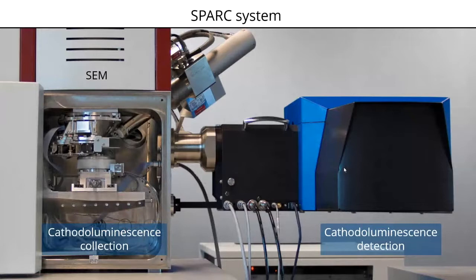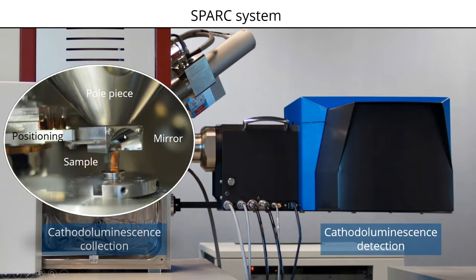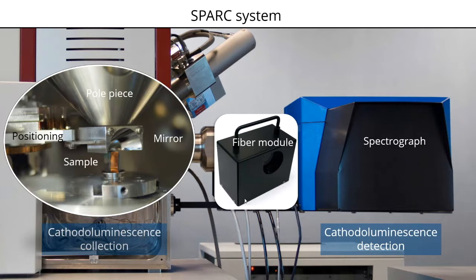Now let's move to some practical things — how do you actually do time-resolved cathodoluminescence imaging? You have an SEM, either pulsed or continuous. Inside, cathodoluminescence collection is done by a parabolic mirror connected to a motorized stage, which you can use to align the mirror or retract it. Outside there is optics in the detector unit, including a spectrograph for spectroscopy and angle-resolved imaging. In this optics compartment there's also a place for a fiber module, which allows you to couple light into a fiber and guide it toward an external detector for time-resolved imaging.